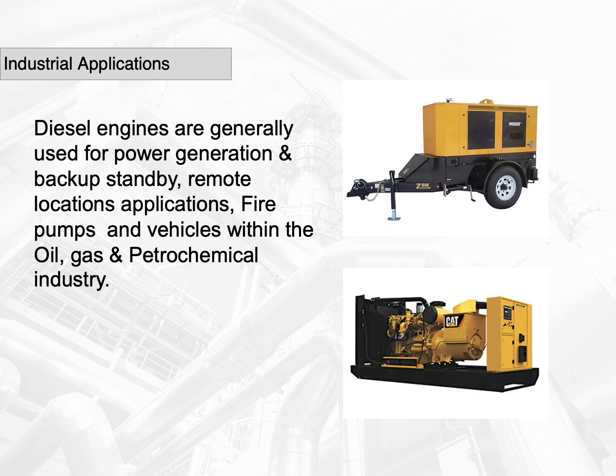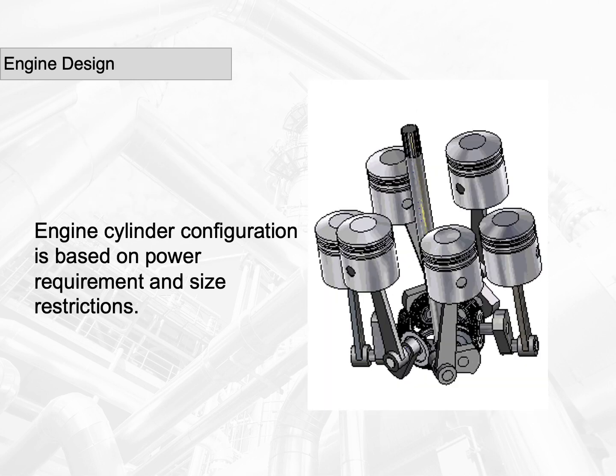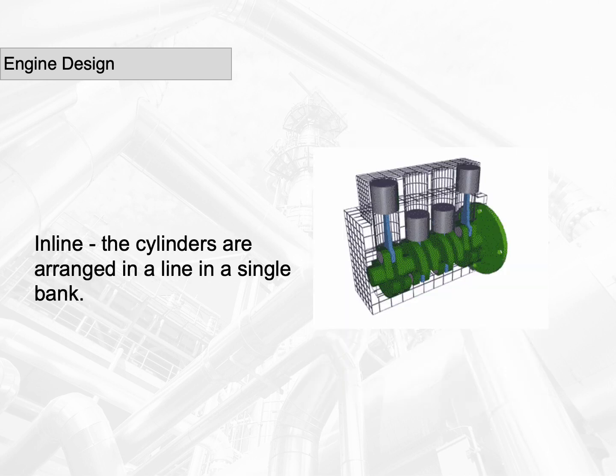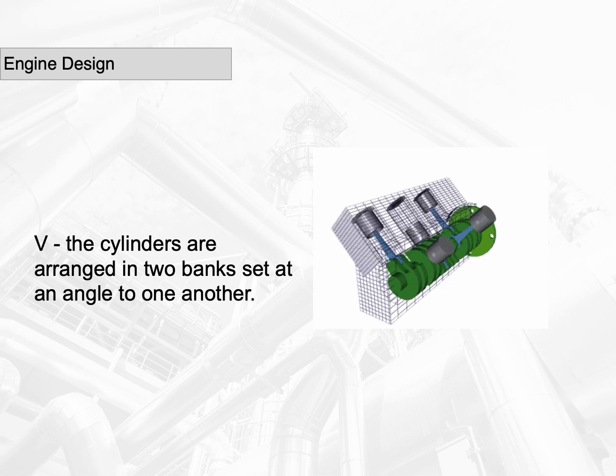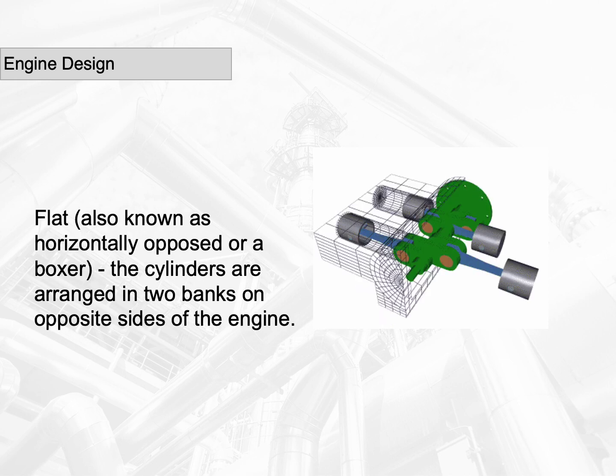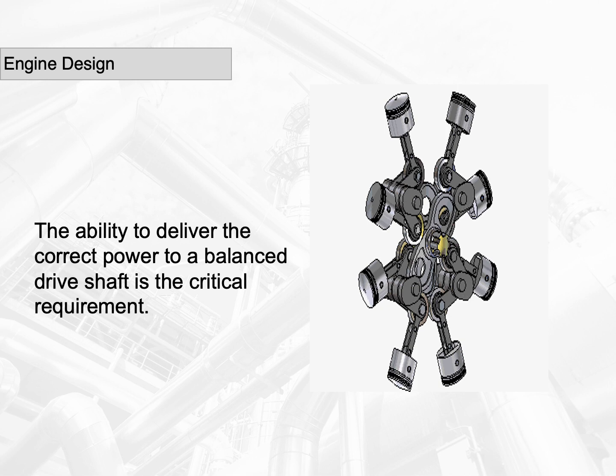Diesel engines are generally used for power generation and backup standby, remote locations applications, fire pumps, and vehicles within the oil, gas and petrochemical industry. Engine cylinder configuration is based on power requirement and size restrictions. Inline: the cylinders are arranged in a line in a single bank. V: the cylinders are arranged in two banks set at an angle to one another. Flat, also known as horizontally opposed or a boxer: the cylinders are arranged in two banks on opposite sides of the engine. The ability to deliver the correct power to a balanced drive shaft is the critical requirement.